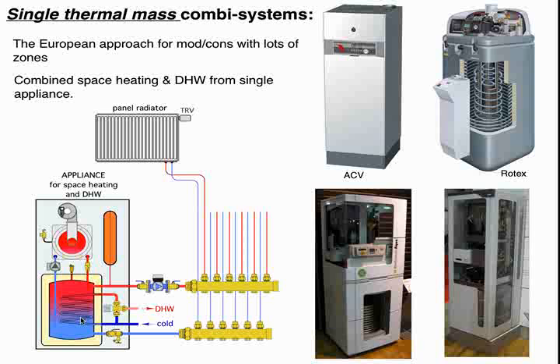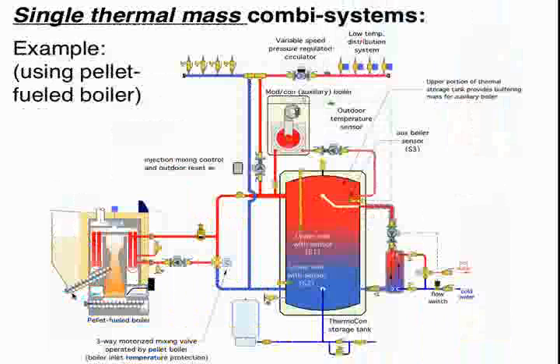Some of you may remember the old boilers with tankless coil water heaters, where the boiler always maintained a higher temperature, even during a hot summer day. Might have a boiler sitting at 160 degrees, because cold water would come in and would make one pass through that coil and then go off to the load. Well, think of this as a tankless water heater on steroids. This is a much bigger coil, so we don't have to have the water in the tank as hot. Obviously, if we want, let's say, 120-degree water to the taps, we probably are going to have to maintain this water in this tank at maybe 125 to 130 degrees Fahrenheit. But we only have a single thermal mass there that is buffering space heating, as well as providing an instantaneous source of heat through that coil heat exchanger for domestic water heating.